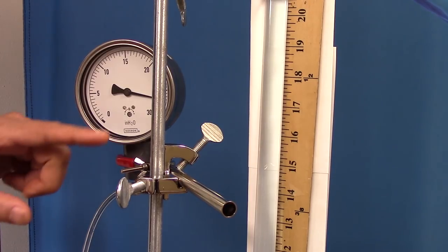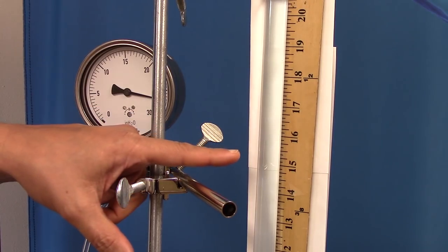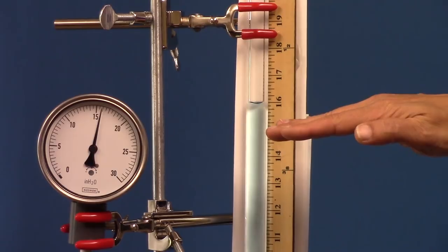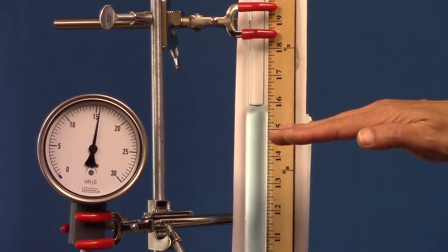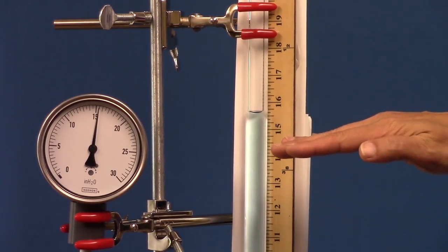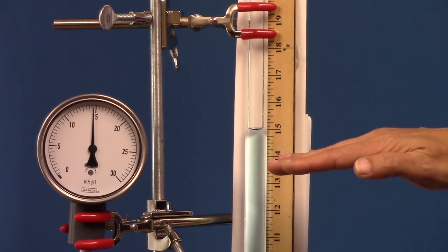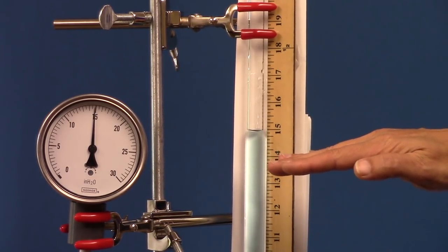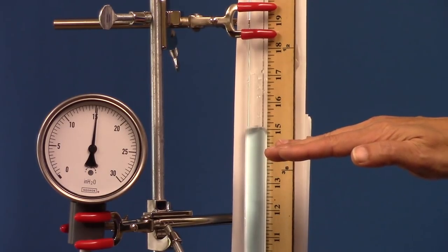The column of water is measured by this yardstick. So to demonstrate the resolution of the Equilibar back pressure regulator, I'm going to control from 16 inches of water column down to 15 inches of water column, and then I'm going to bring it back up to 15 and a half inches of water column.